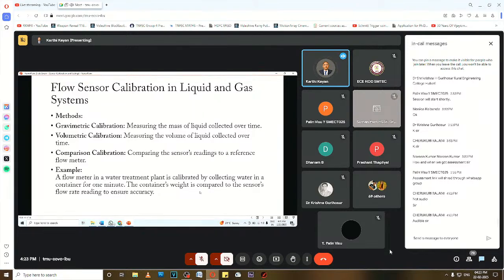For example, a flow meter in a water treatment plant is calibrated by collecting water in a container for 1 minute. The container's weight is compared to the sensor's flow reading to ensure accuracy. Not only 1 minute, but 2 minutes, 3 minutes, 5 minutes, 10 minutes. They will continually check the flow meter readings so that we can accurately tell whether it has sensed correctly or wrongly, and understand whether it is perfectly done or not.